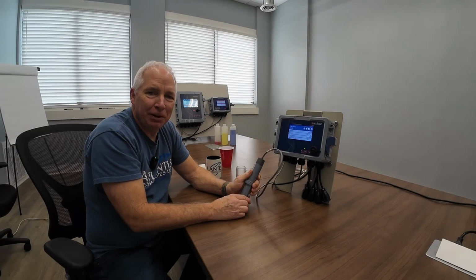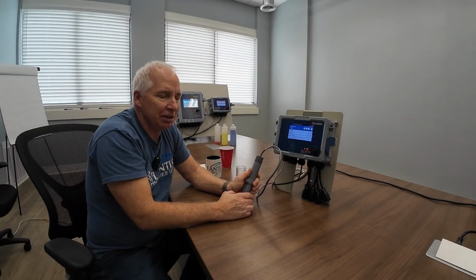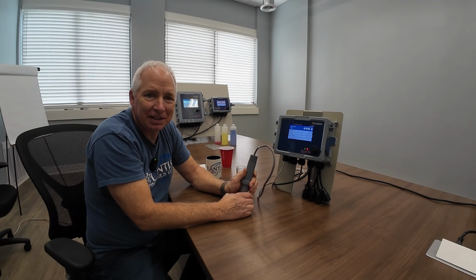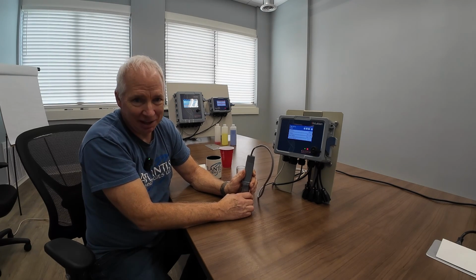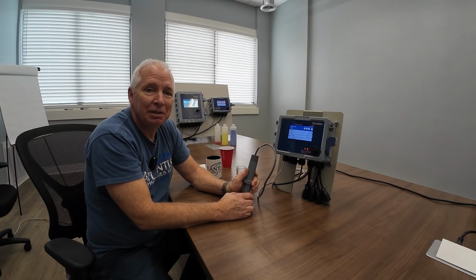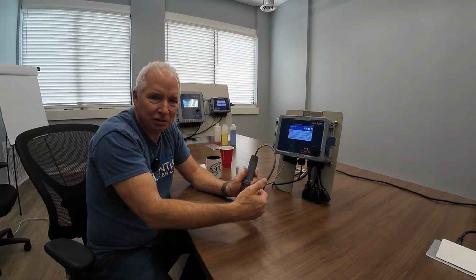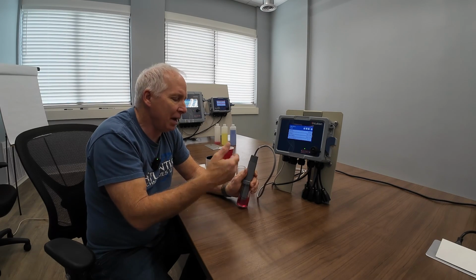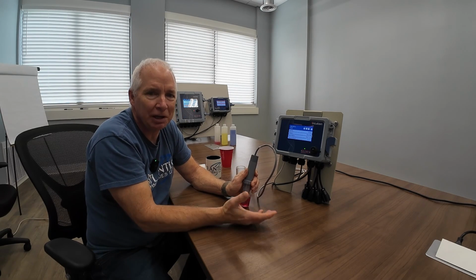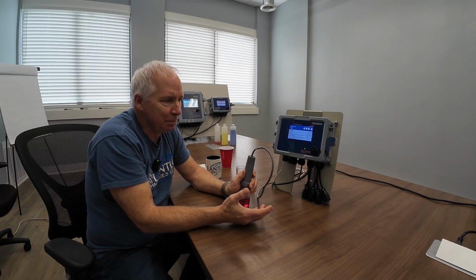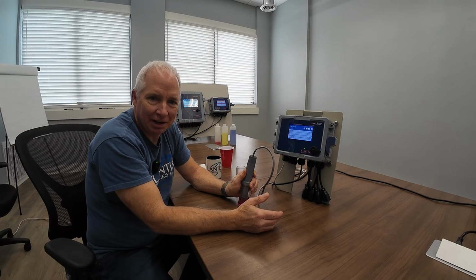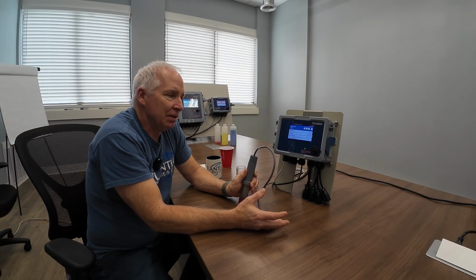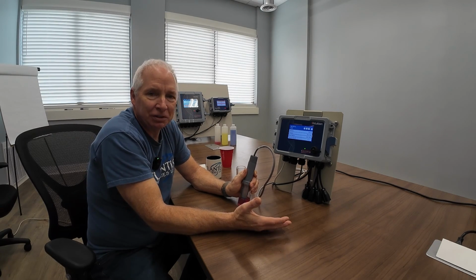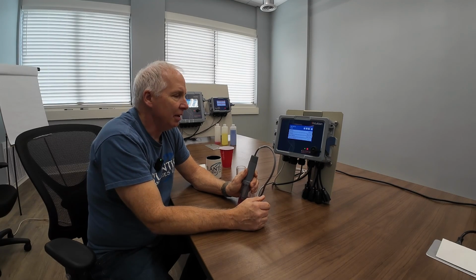So if you failed a calibration, you take a look at those millivolt readings. That'll give you an indication on whether you should try this again. Maybe you were too fast. Maybe whenever you actually were going through this, you didn't let it stabilize enough. And then when you went back and put it in your test buffers, it was not even close. So that could be something where you didn't take enough time between allowing it to go ahead. And that's something that, I think the more patience you use, the better on that.